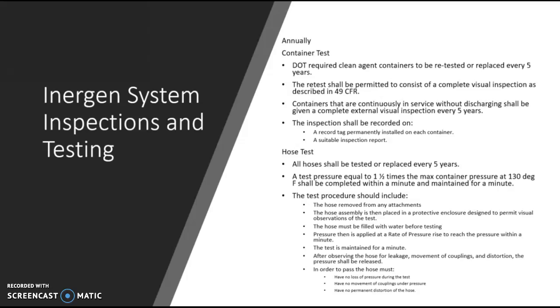It says 1.5 times the pressure limit. You fill it full of water, and then the water is pressurized for a minute, and it has to pass for a minute. And in order to pass, it must have no loss of pressure during the test, have no movement of couplings under pressure, and have no permanent distortion to the hose. And these are the PM requirements that you would have for your facility.